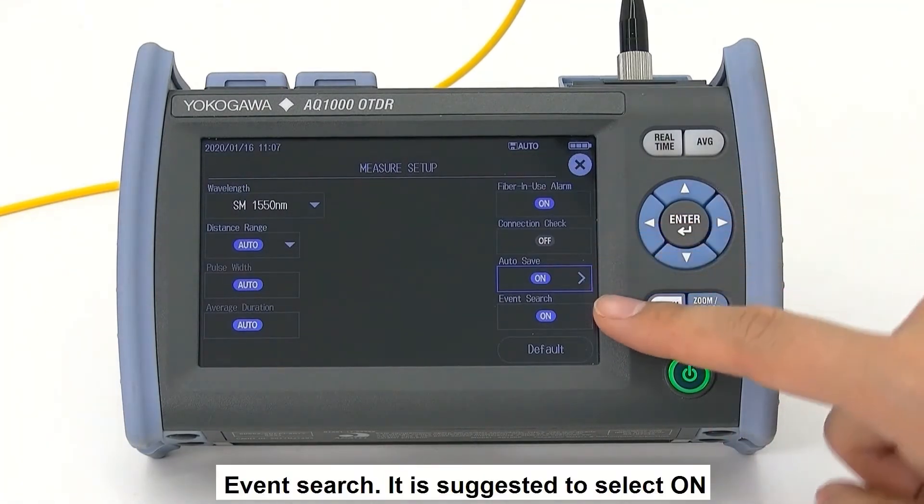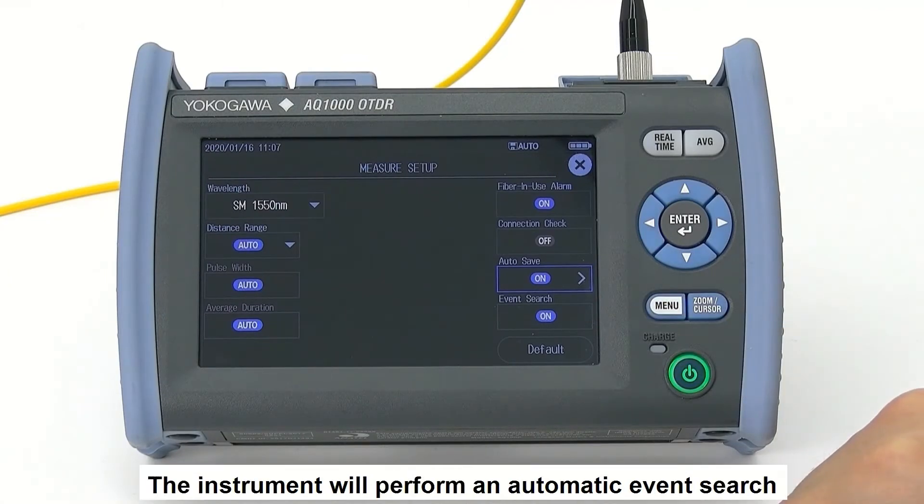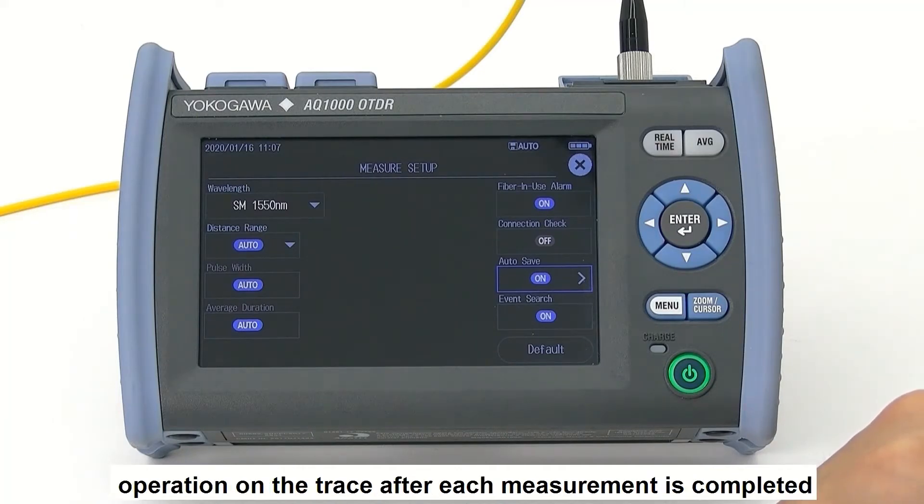Event search - it is suggested to select on. The instrument will perform an automatic event search operation on the trace after each measurement is completed.